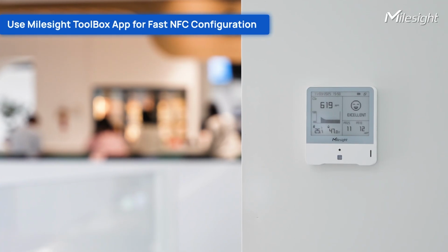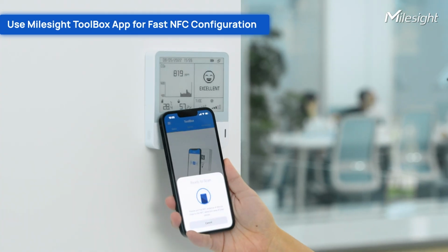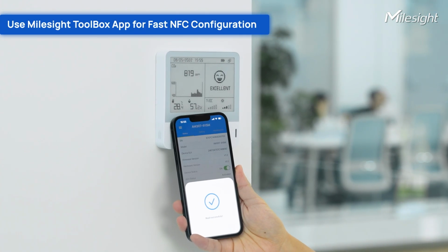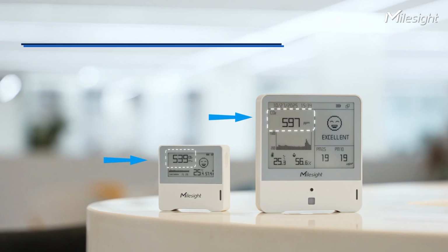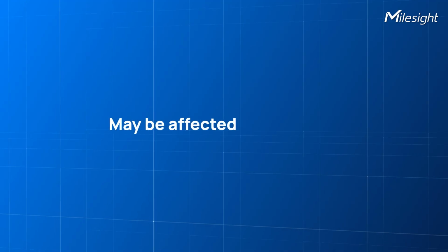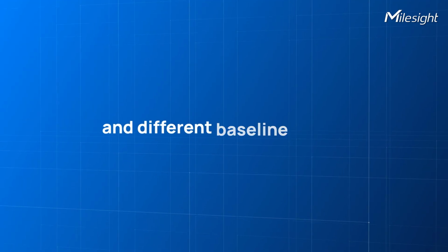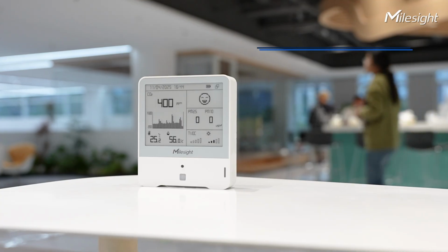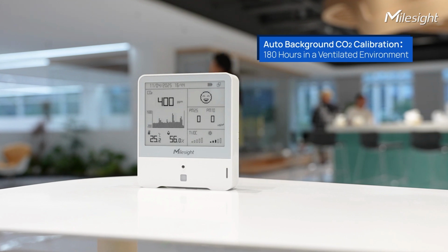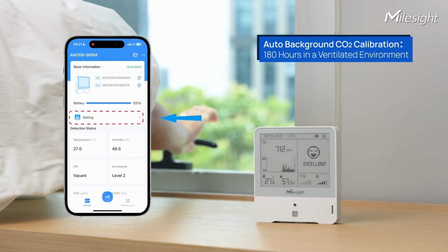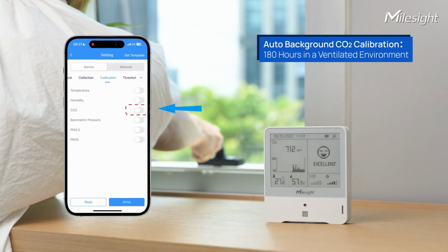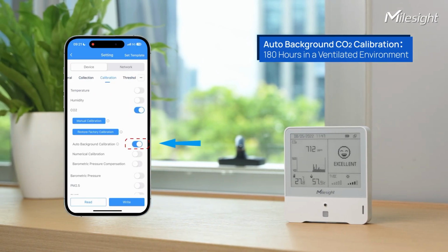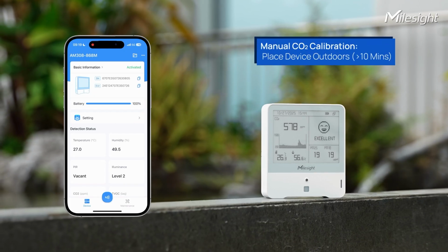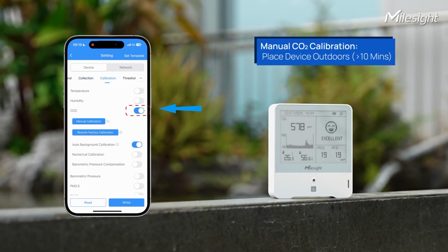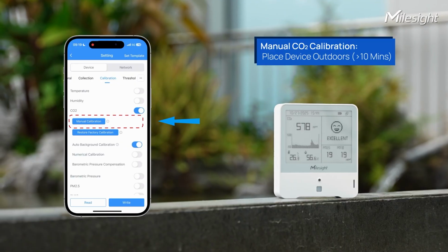AM series sensors support NFC configuration. Use the Milesight Toolbox app to quickly set parameters or network connection information. The accuracy of carbon dioxide detection may be affected by shaking during transportation, and different baseline values and environmental humidity will also affect the detection results. AM series sensors support auto background calibration function. Turn on this function and ensure the device has regular ventilation in the days following installation so that the device can better learn the baseline value. You can also put the device in an open outdoor environment for more than 10 minutes and click the manual calibration button to calibrate the CO2 value.